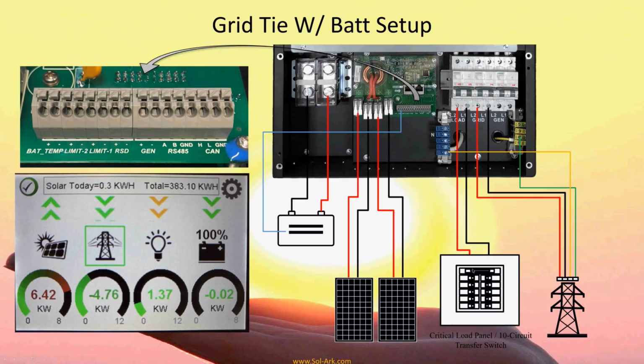And then we'll have a critical loads panel or a 10-circuit transfer switch on our load output. This is our UPS output. And there's a little bit of programming involved with this. So this is going to run on grid and power those loads. Oh, notice that this is 12 kW pass-through. So that's how much our loads in our grid can be. The inverter can only do 8.